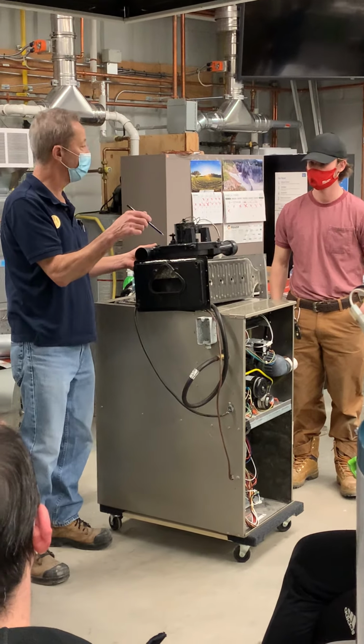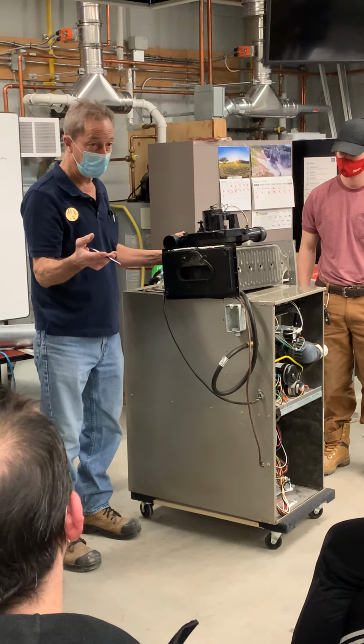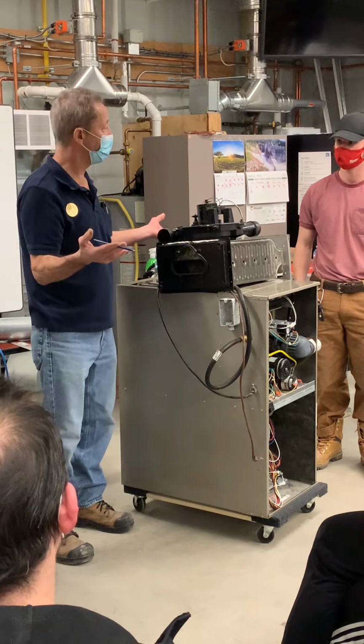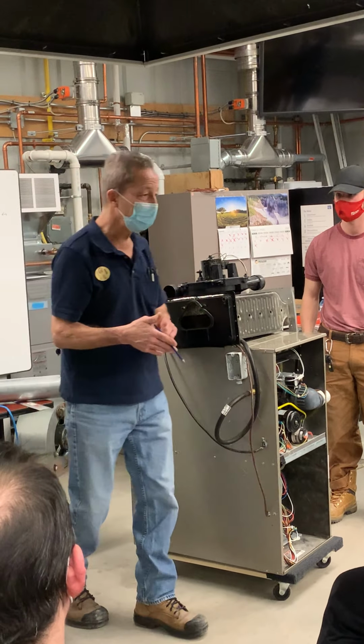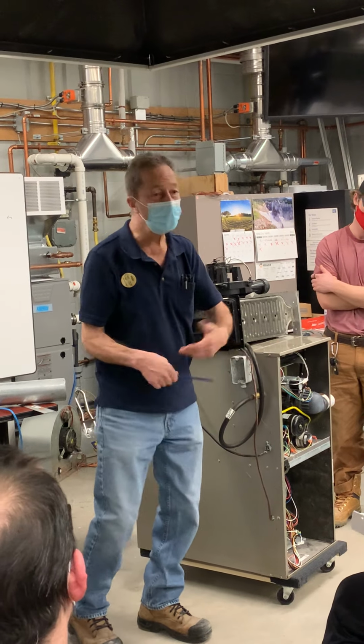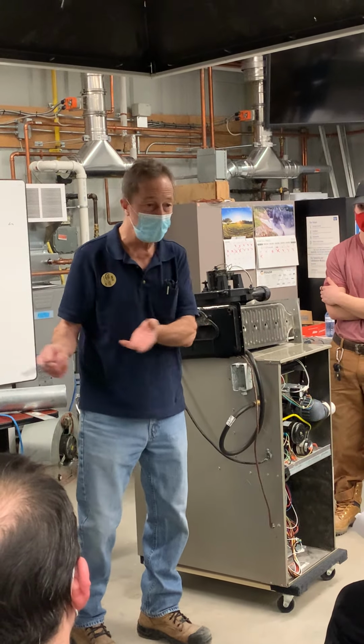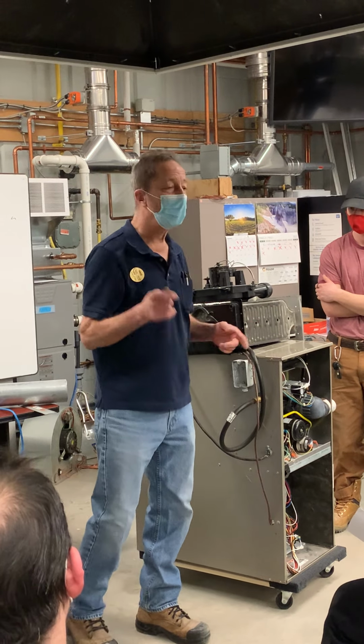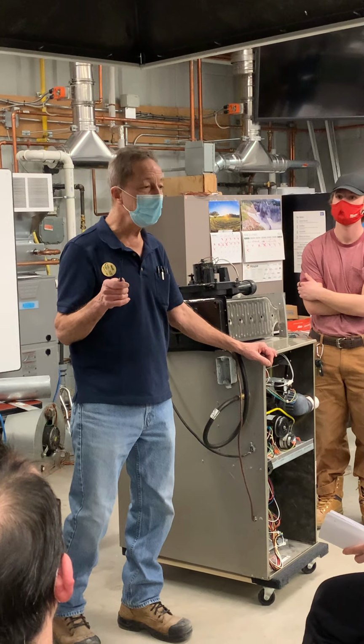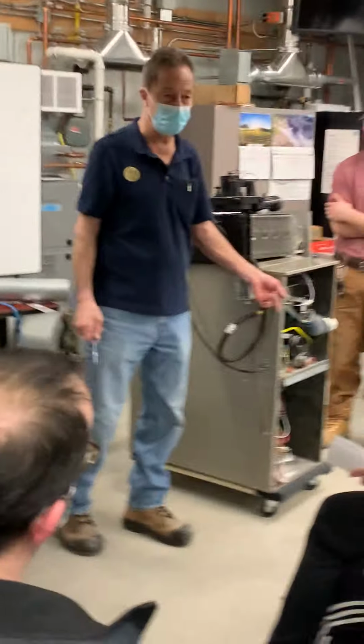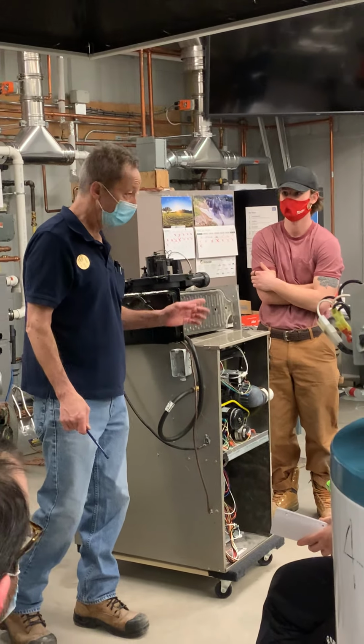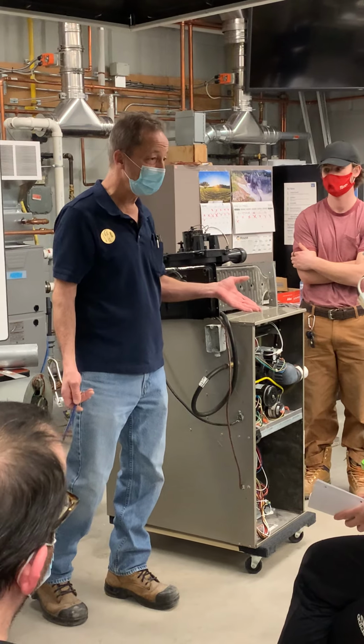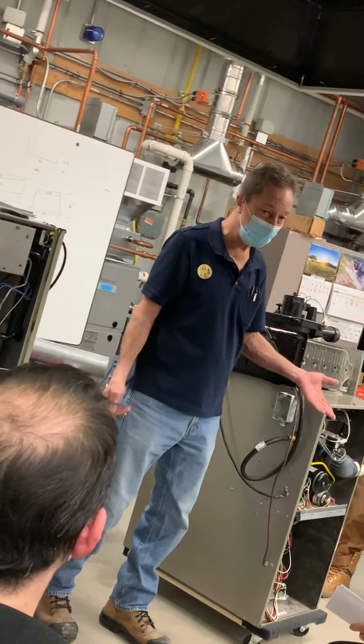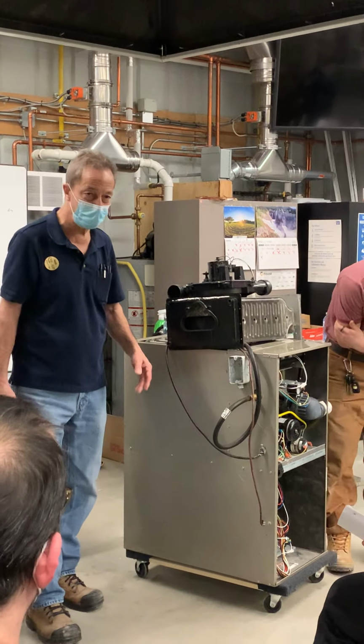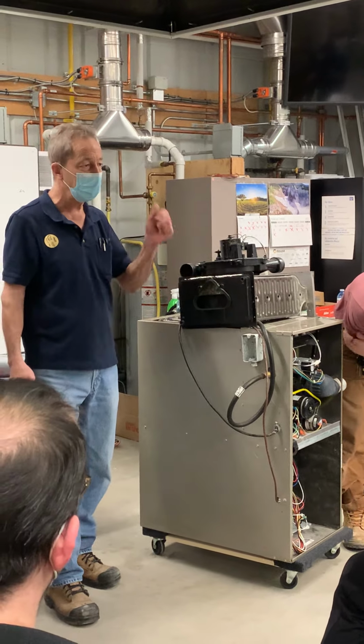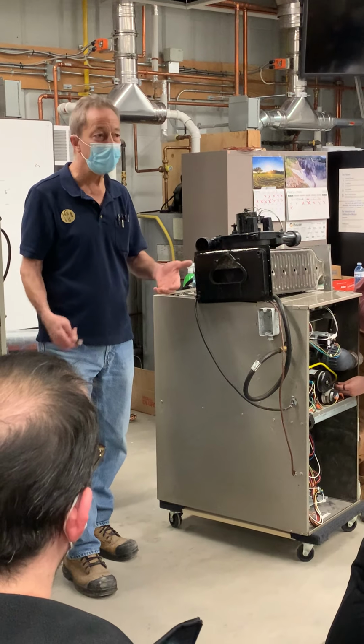What does this pressure switch respond to? Negative pressure. And it causes the contact to close. So once the contact closes, the appliance thinks, good, let's get going. It's time to go. We're going to start the sequence of operation. Fair enough? Now, if I've got a blocked secondary heat exchanger, will the pressure switch see negative pressure? You said yes earlier. Yeah, it will. It's still going to see negative pressure. So the pressure switch says, yeah, I'm seeing negative pressure. I don't care that it's a blocked secondary heat exchanger. The inducer's running, it's sucking, it's negative pressure. Let's get the show on the road. So what happens? It fires the appliance.